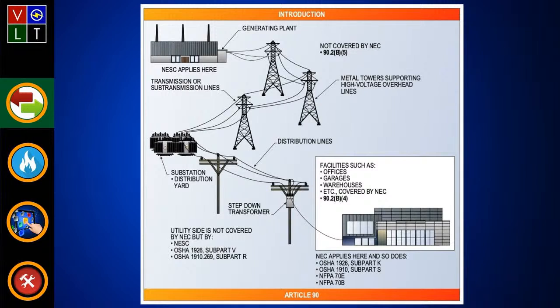And I'll get into this more in my slides, but there's a lot of confusion. I'll go into a substation to do audits for a client, and I'll see a guy standing there hanging grounds on a de-energized bus with a stick in his hands, wearing a 40-calorie suit and class 4 gloves. When I talk to the owners, they say, well, that's what 70E requires. There's a tremendous amount of confusion about where these standards are separated.